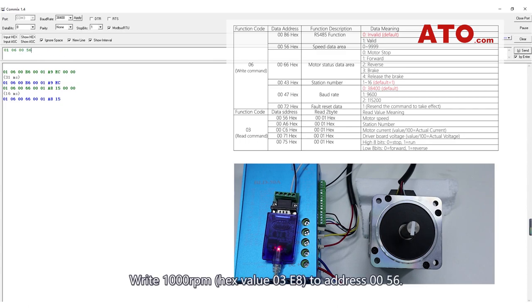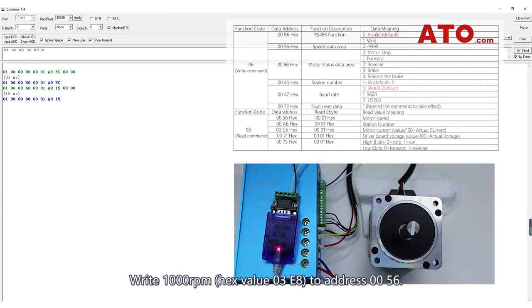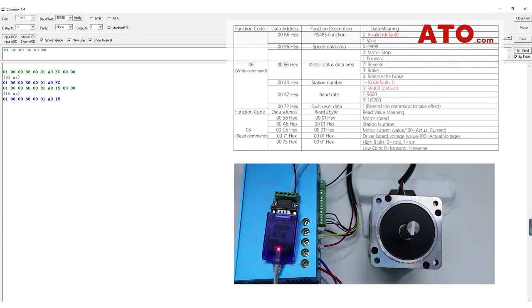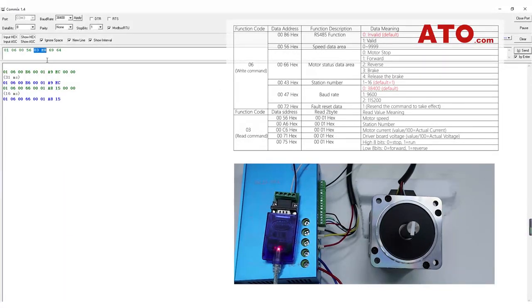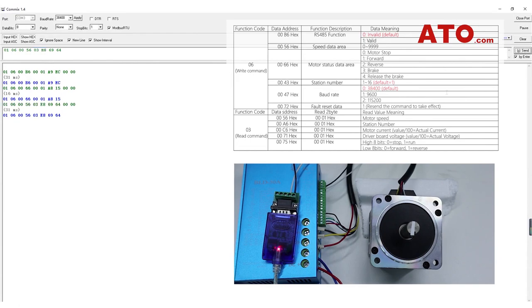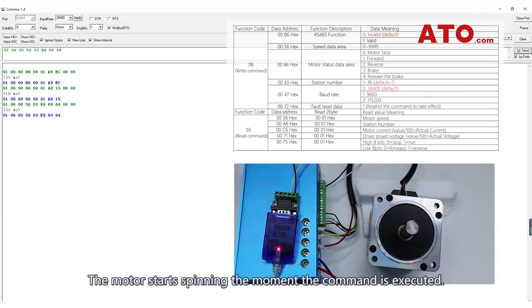Write 1000rpm hex value 03E8 to address 0056. The motor starts spinning the moment the command is executed.